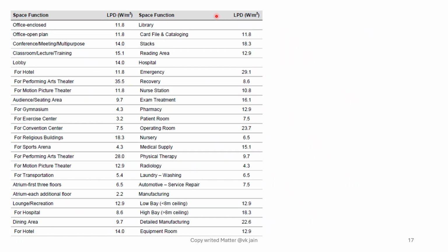The ECBC code provides another concept also. Here the lighting power density should not be more than whatever is provided, but here it is by space function of a particular section of a building, say lobby for hotels, for office certain portion, then hotels, then other types of building. So this space function gives you power requirement for lighting, for reading area, in case of hospital, emergency, recovery, nursing station, exam, and so on. So you can choose any of the two methods, space function method or building load function method.